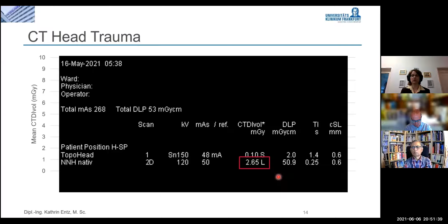It is used here by the scanner to compute, or to calculate, the CTDI vol, and we are actually doing a scan of the head. Using the larger phantom, the body phantom, in this case would be completely wrong. So the dose is underestimated, or calculated too low, just because the wrong phantom was used. You can simply correct it by using a conversion factor to get from your large phantom to your small phantom. Then instead of a value of something like 2.6, you're now at 4.4, which is a bit higher, still below this value, but at least you now have the correct value.